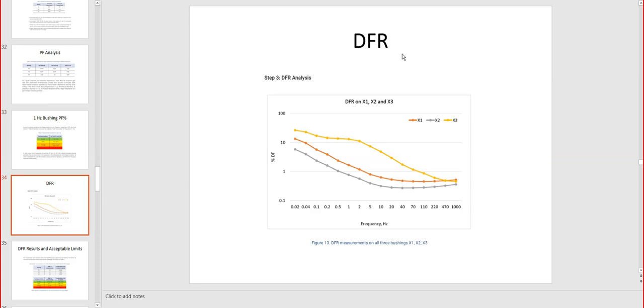DFR, the dielectric frequency response analysis that we got on the same 3 bushings on the MOT. These are the graphs for the 3 phases, and we can see that 2 of them are pretty close to each other, with the same shape, but one is way off, with higher values and a different shape.